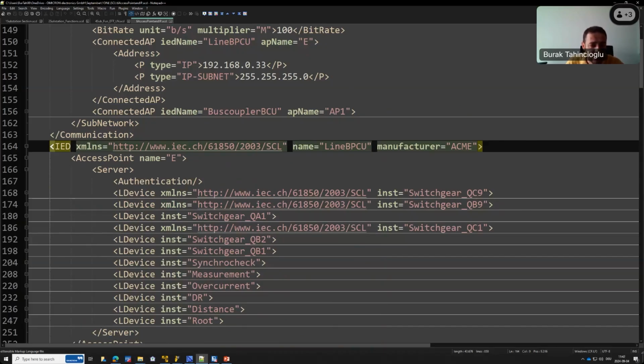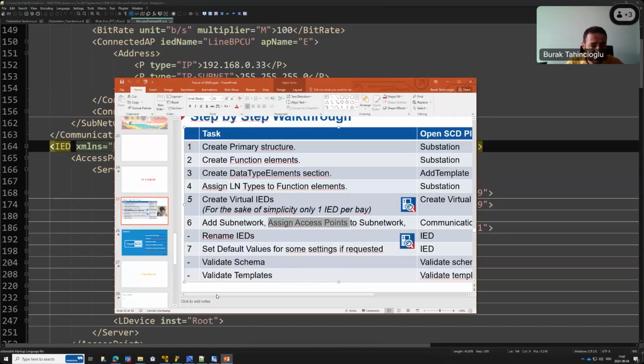We haven't defined any GOOSEs, reports, and sample values. That's possible, actually. We can also define the specification, the communication services, the GOOSEs, the data set, everything. But we have to save some time. Just be informed that it's also possible to specify the communication services. Then there is really nothing left except to find the right physical IED matching with your specification, which consists of data model, communication flow, communication parameters, more or less everything.